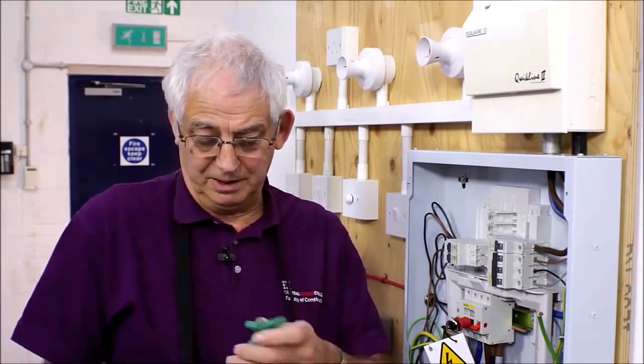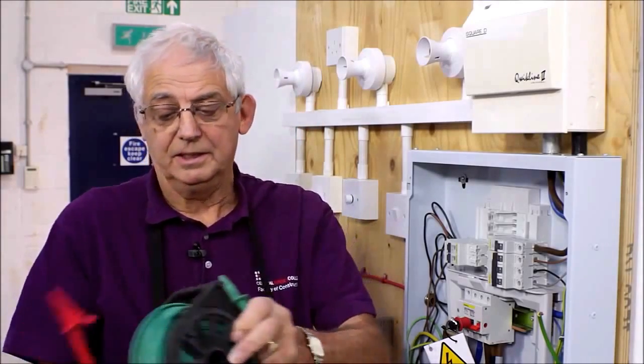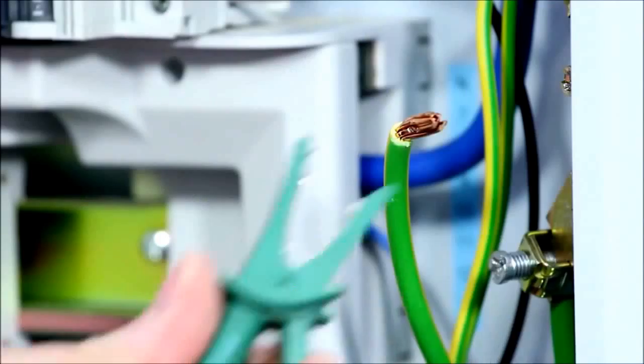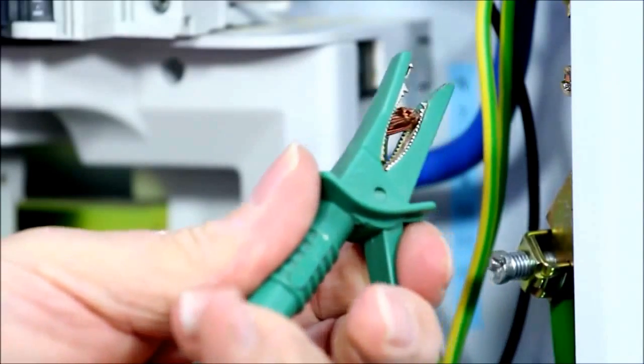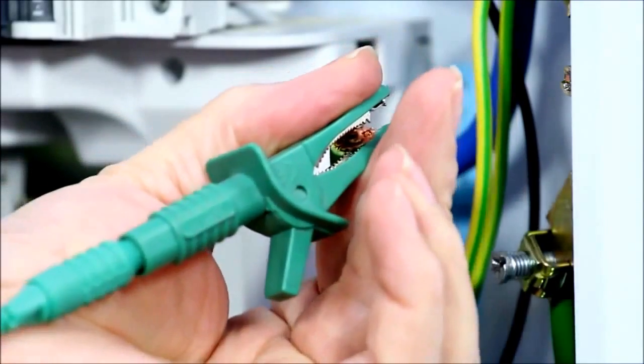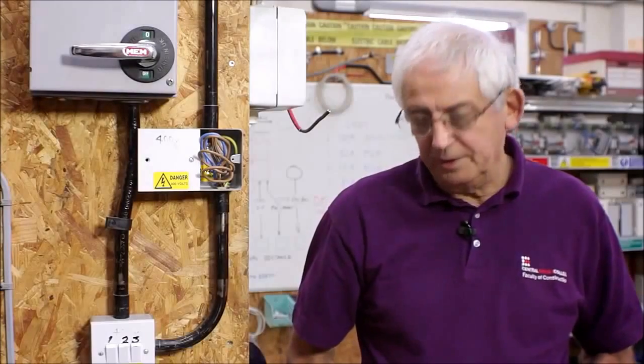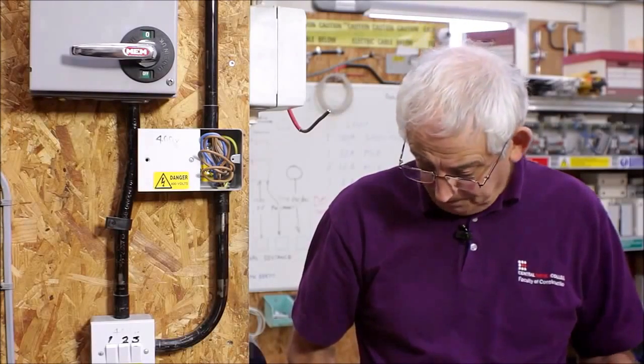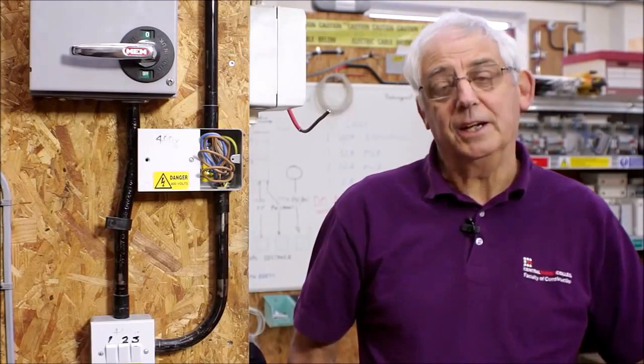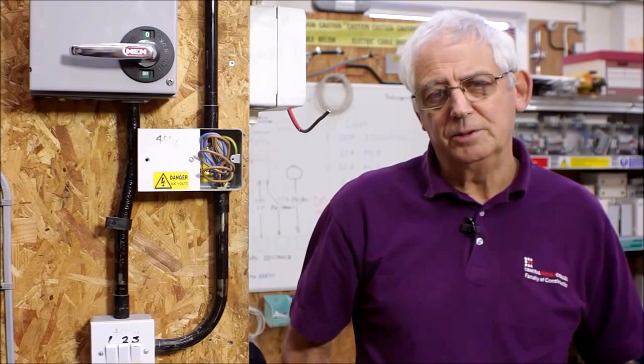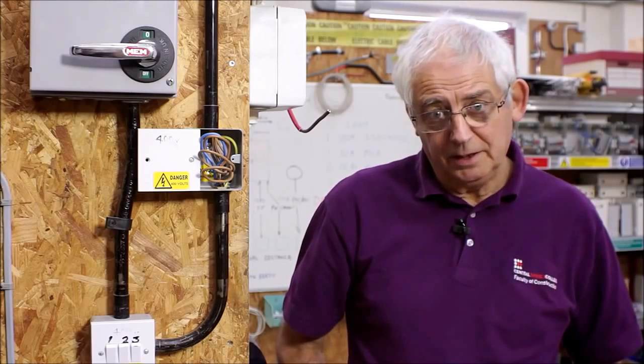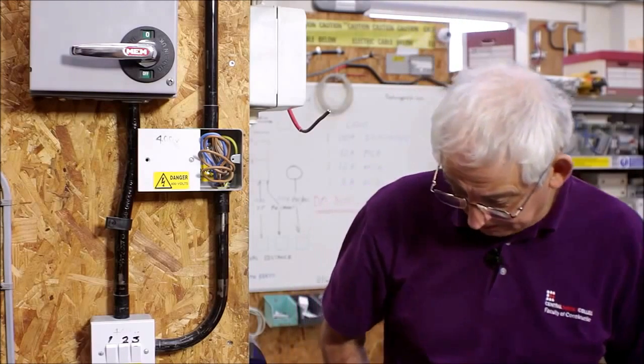First thing I need to do then, of course, is connect the end of my green lead to the disconnected bonding conductor. And this is bonding the gas. And then I need to go off and find the gas meter and do another test at the gas meter. So now we're at the gas meter. Just going to carry out the final part of the check, and of course that's to measure the resistance of the main protective bonding conductor.